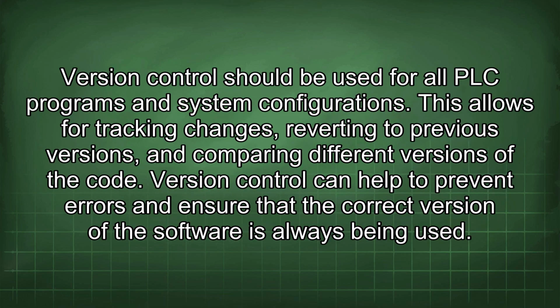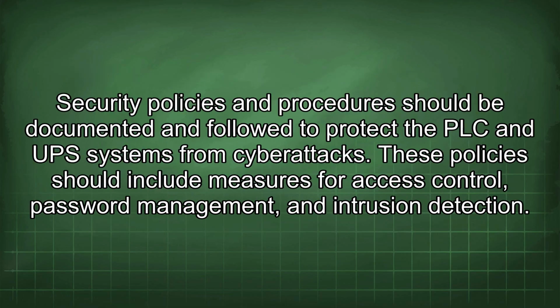Version control should be used for all PLC programs and system configurations. This allows for tracking changes, reverting to previous versions, and comparing different versions of the code. Version control can help to prevent errors and ensure that the correct version of the software is always being used. Security policies and procedures should be documented and followed to protect the PLC and UPS systems from cyber attacks. These policies should include measures for access control, password management, and intrusion detection.